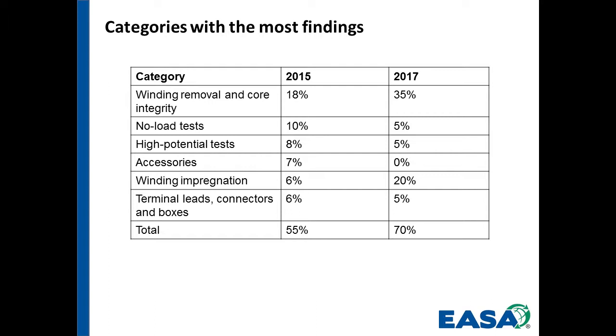The findings. In 2015, I went through, again, statistical, not 100%. Although, actually, I take that back. In 2015, I think I went through every one of the audits at that point in time. By 2017, there simply were too many audits to keep doing that, so it became a statistical approach. But what was found was winding removal and core integrity, the removal of the windings. We can see those high percentages, 18%, even higher in 2017, 35%.